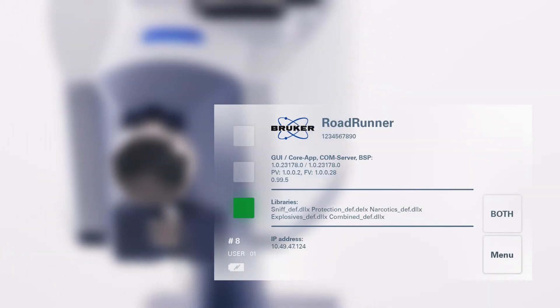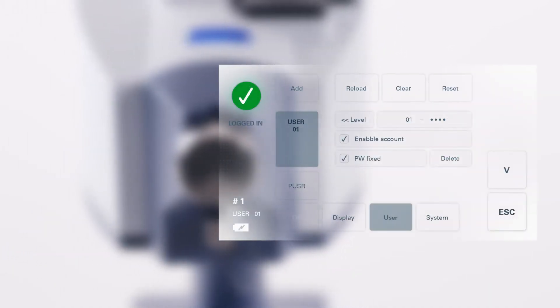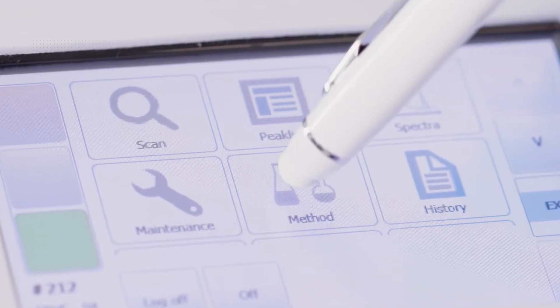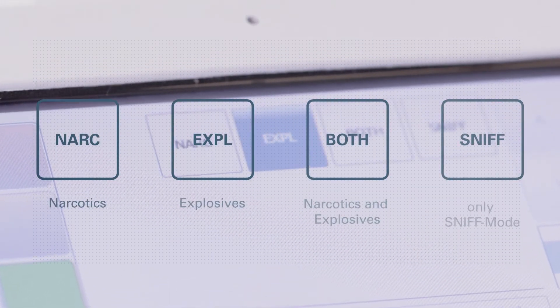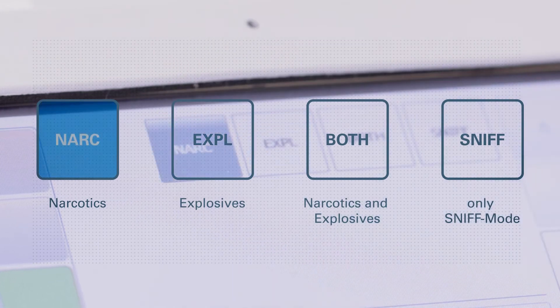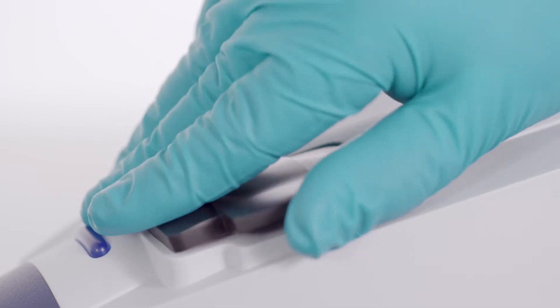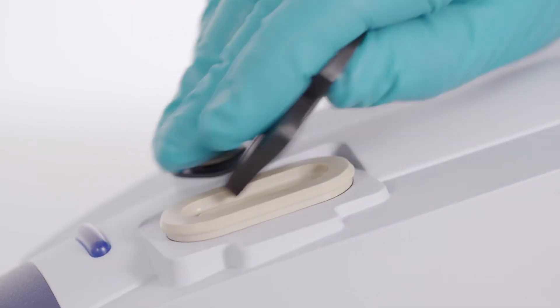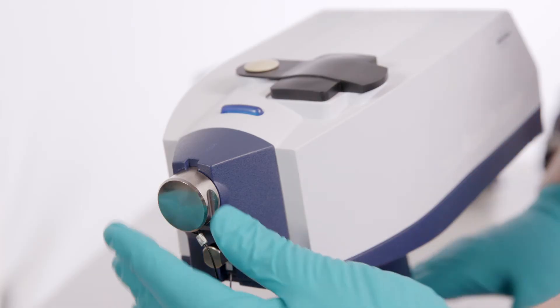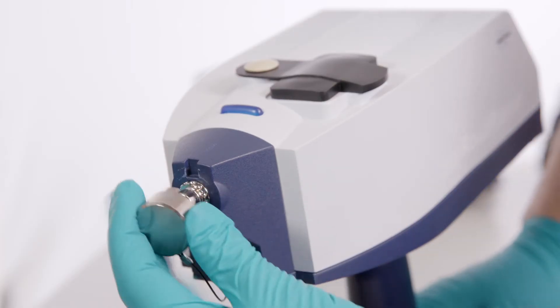Once ready, indicated by a green tick symbol and instructions to sample, the operator chooses sniff or swab. Opening one of the two inlets will automatically trigger the Roadrunner to be ready to sample in the correct mode.